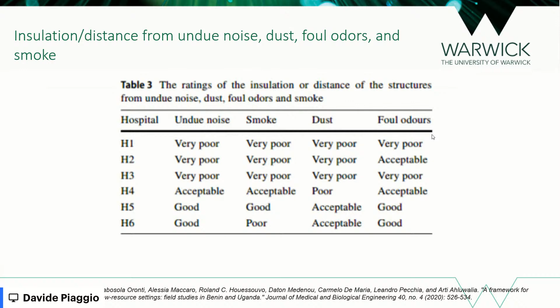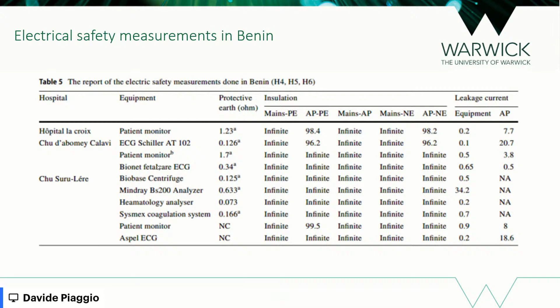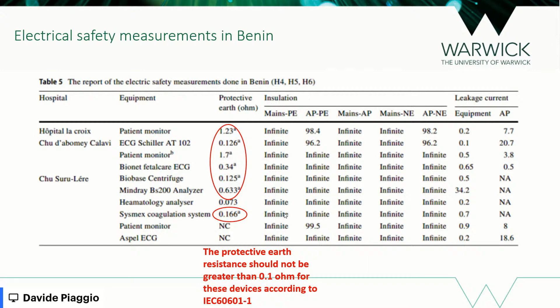These are the results of the electrical safety measurements. I won't bore you too much with this information, but what clinical engineers normally measure is the protective earth of the device, the insulation, and the leakage currents, which have to be within certain thresholds set out by international standards. In this case, we tested the devices that we were given the opportunity to test. What we could see is that while all the insulation leakage currents were okay, in terms of protective earth, some of these devices, the ones in red, were out of the standard, which means that there could potentially be a risk for the user.